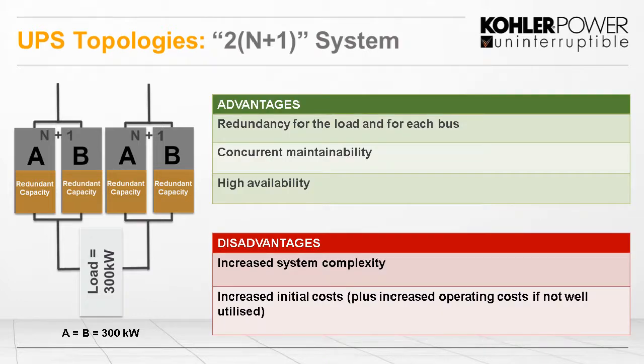So the advantages now, obviously, are that we have redundancy for the load at each bus. We can maintain any single UPS in there concurrently, and we have extremely high availability to the load. And we'll talk about that just later. The disadvantages are, obviously, much more complexity in this system. And initial costs are high, obviously, because you're buying so much, but they can increase further if we don't have that running in the efficient mode I talked about with the utilization.